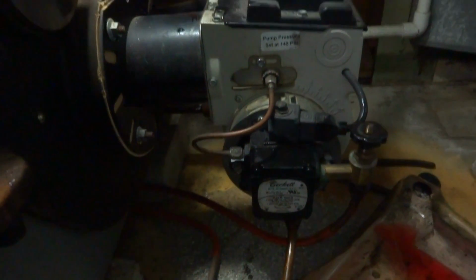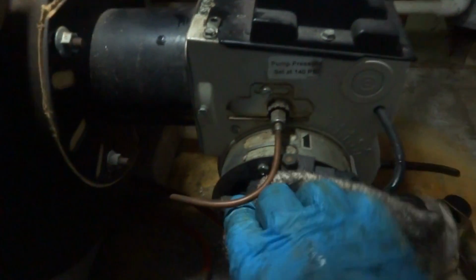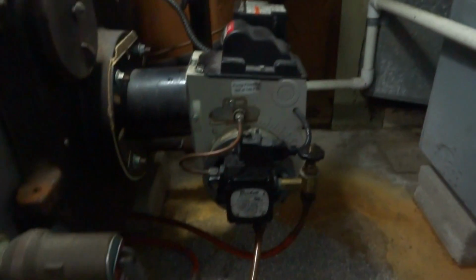Pumping. How long has it been since he changed the nozzle? Like I say, I had Eddie do that, and Sylvia do that oil. He's retired now? Yeah, he retired. And Eddie and I do it. That's how I always had it. Eddie was always very thorough and always took good care of me because of the connection. Right. Yeah, it might have been an issue with the pump. Usually they don't bind up like that, but that's what the case was. We freed it up and she's firing up nice now.